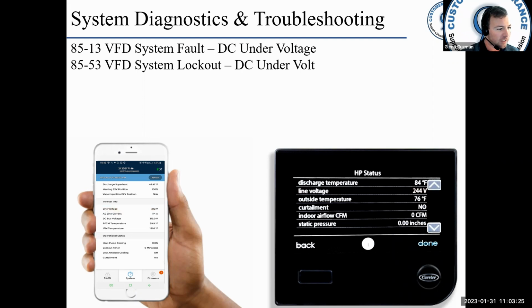What are you reading? If the DC voltage is lower than the acceptable lower limit, which is 180 volts DC, after 4 occurrences within 1 hour, you get the 8553, which is a 2-hour lockout. Okay. 8513 is usually accompanied by a VFD reset. This can happen due to low AC line voltage, quickly loading the compressor, or a damaged PFC circuit in the VFD.